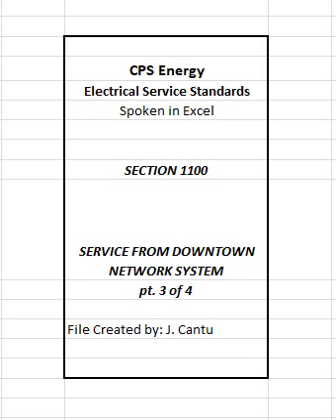5. Where required, customer shall furnish pre-drilled bus bars and copper flags for fuse pad connections. The connection surfaces of bus bars and cable connections must have appropriate plating for corrosion protection. CPS Energy will make all connections on fuse pads. 6. Bus bars to fuse pads must be insulated beyond fuse pad panels. 7. Low impedance bus bars and customers' conductors must be unscrambled, all like phases to come together.